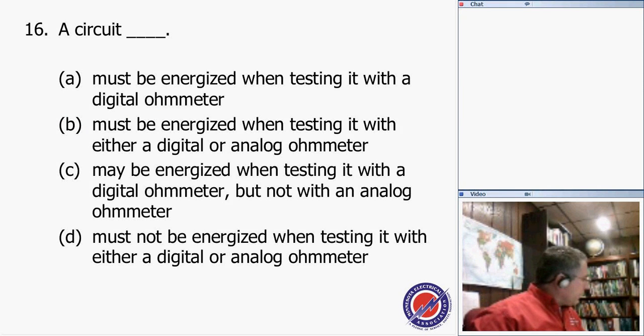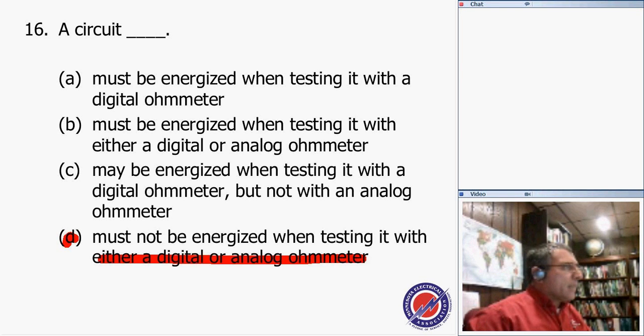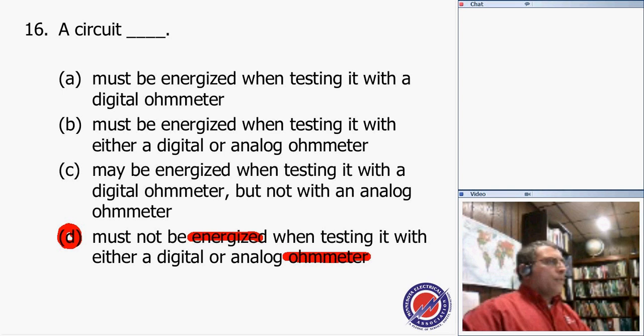Number 16, friends, a circuit must not be energized when testing it with either a digital or analog ohmmeter. So D is our answer for this one. The key point here is energized, and second, ohmmeter. We're measuring the resistance. You know, my friend, you can't measure the resistance when the circuit is hot. Resistance is a phenomenon that is always measured when the circuit is de-energized.